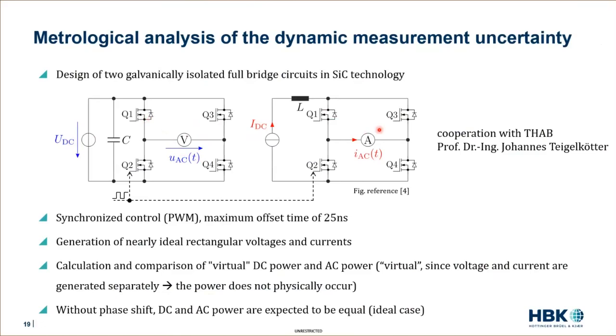So AC signals. If the PWM is synchronized, meaning the rectangular output signals are synchronized, then I can calculate what I call a virtual DC power, because the power is nowhere in reality since the two measurement circuits are galvanically isolated, but we can calculate a power from the DC signals. If we then also do a power calculation from the AC signals, this should deliver exactly the same result if we do not have measurement uncertainty in our AC measurement.